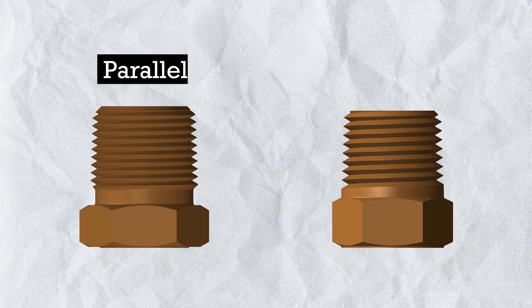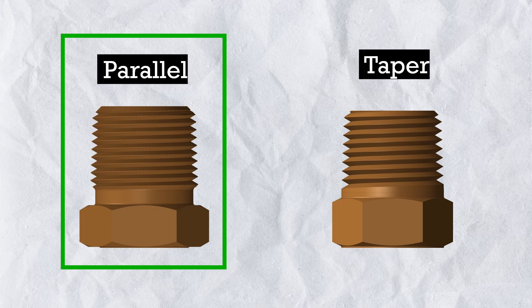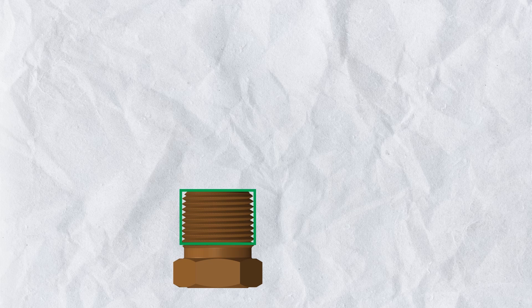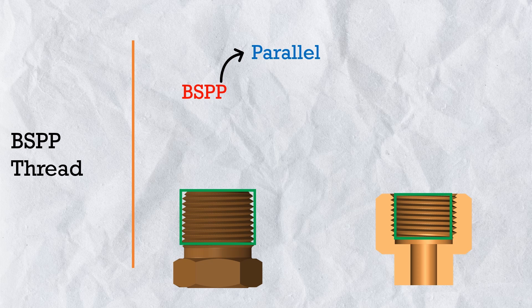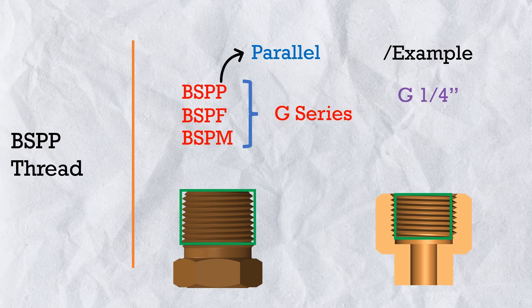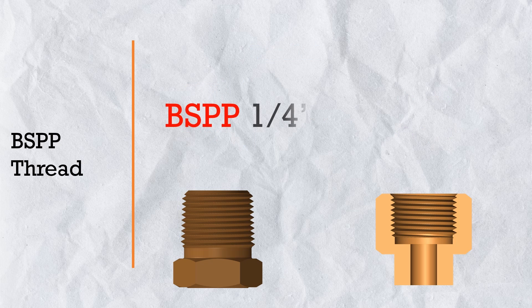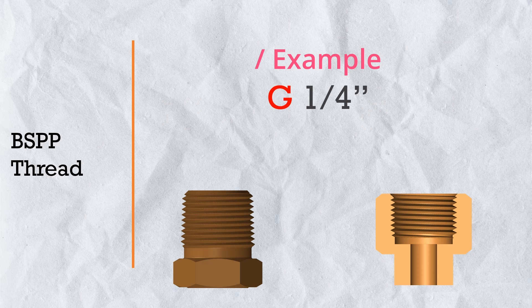The third and most important thing is the shape of BSP thread. BSP threads come in two shapes. The first is parallel thread — a straight thread where the diameter stays constant throughout the length in both male and female thread. We denote it as BSPP (parallel). In earlier times engineers also used BSPF and BSPM, but officially all three standards have been made obsolete and replaced with the G series. We still widely use BSPP as well as G thread, like G1/4 inch or G1/8 inch. BSPP and G thread are exactly the same, but when we write G1/4 inch it refers to both male and female thread, so we should always specify which one.